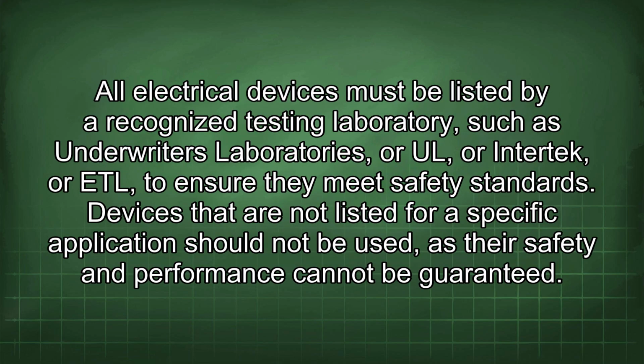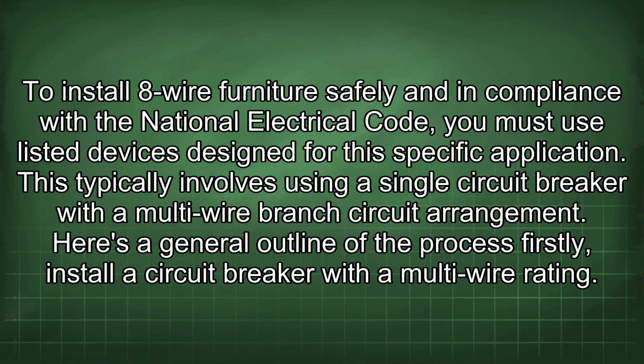All electrical devices must be listed by a recognized testing laboratory such as Underwriters Laboratories, or UL, or Intertek, or ETL, to ensure they meet safety standards. Devices that are not listed for a specific application should not be used, as the safety and performance cannot be guaranteed. To install 8-wire furniture safely and in compliance with the National Electrical Code, you must use listed devices designed for the specific application. This typically involves using a single circuit breaker with a multi-wire branch circuit arrangement.